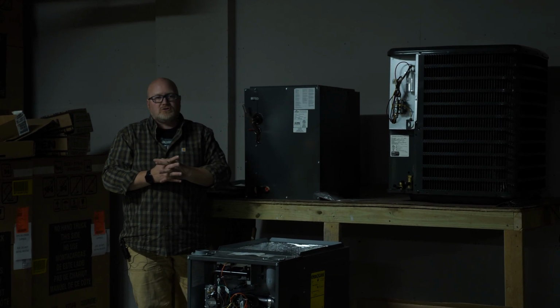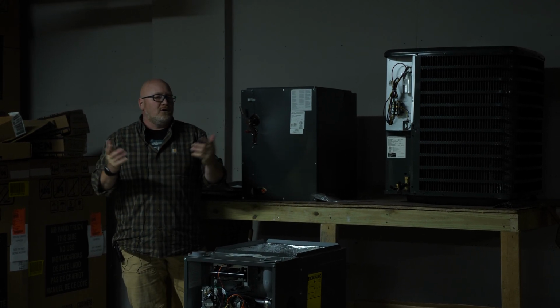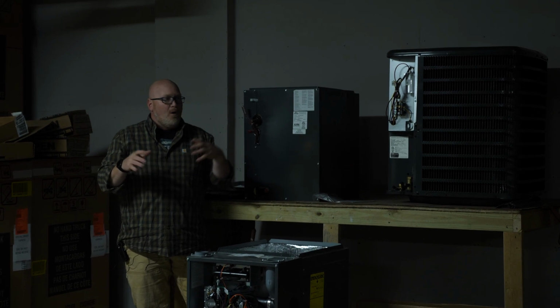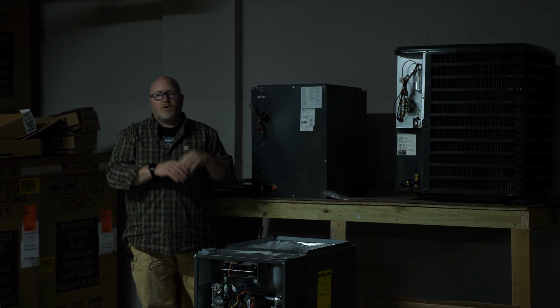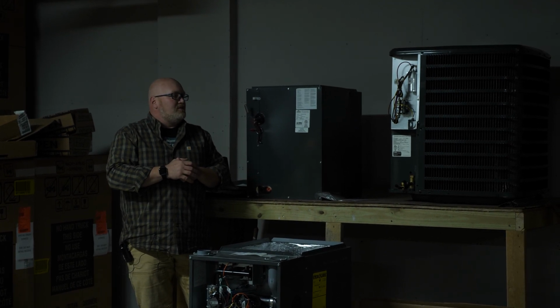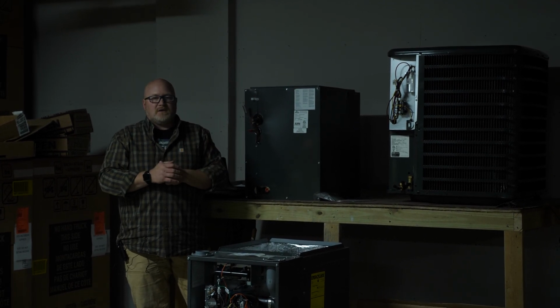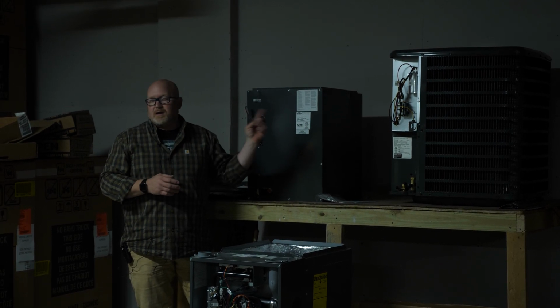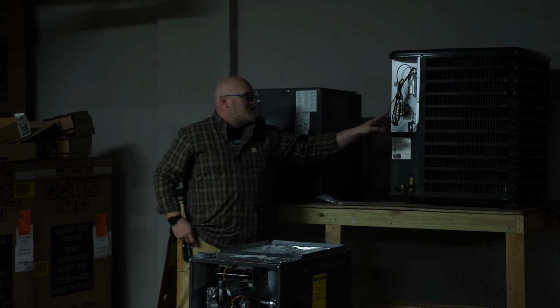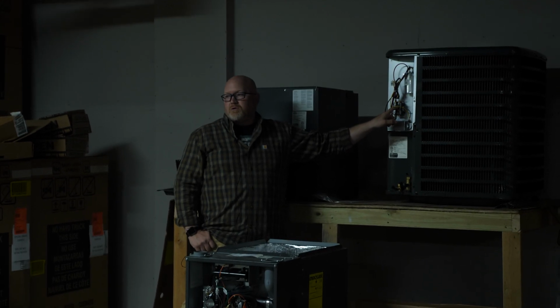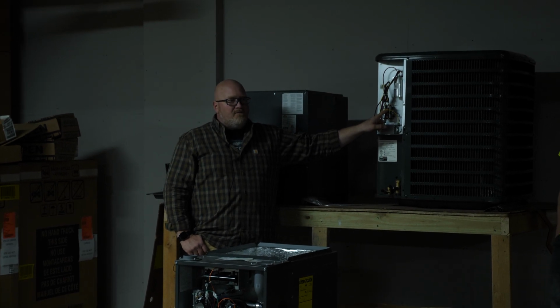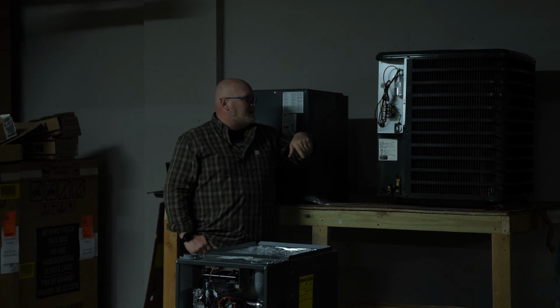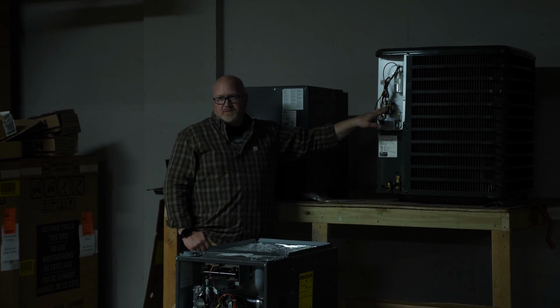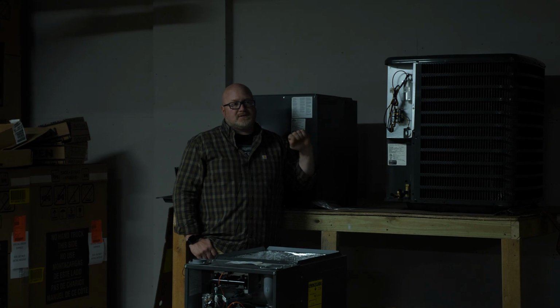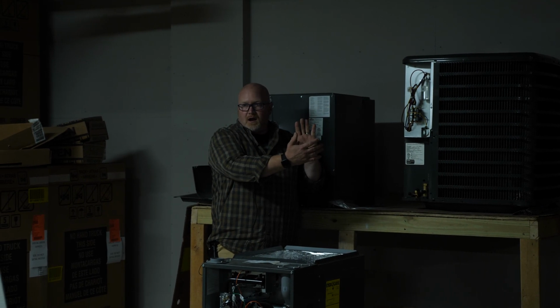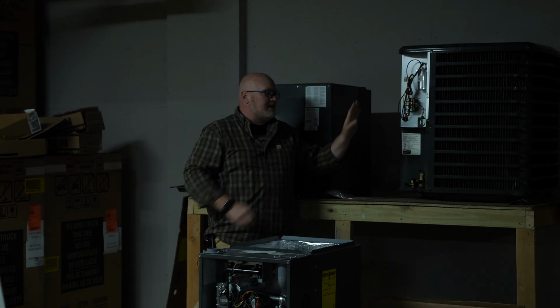Most manufacturers, those contactors, you can get those from a parts store. You won't find any of these parts in a big box store or in a hardware store, but realistically, if you've got access or someone in the trades and they know a little bit about electrical, these parts are not hard to source. Most likely, you can get a part number off of any of these parts and you can order it online. Again, very, very simple parts to swap out and to replace. Obviously, before you would service this or touch this, you would shut off the disconnect, which is the gray box mounted to the side of your house. You would shut off that disconnect, which would disable power to the whole unit.